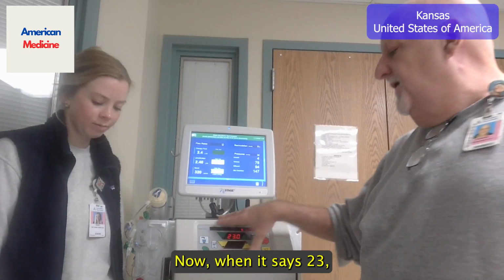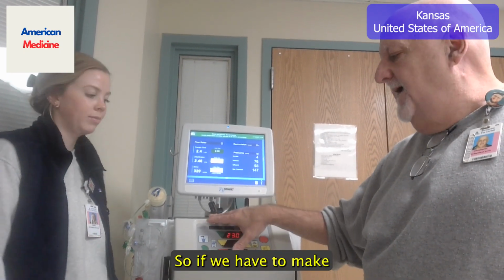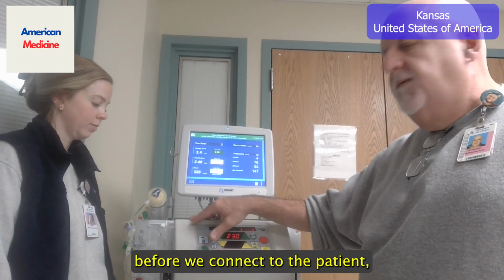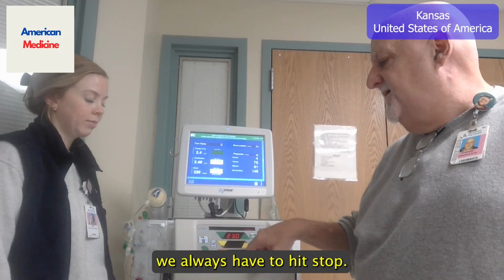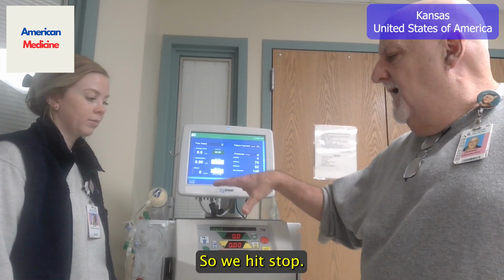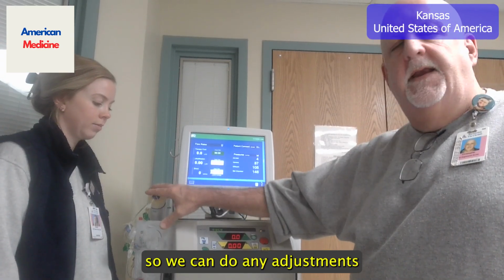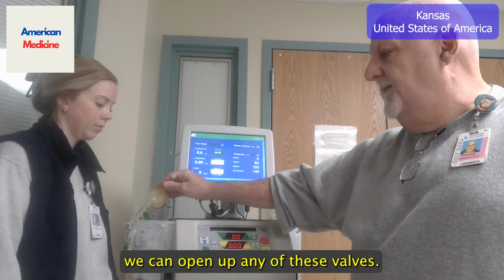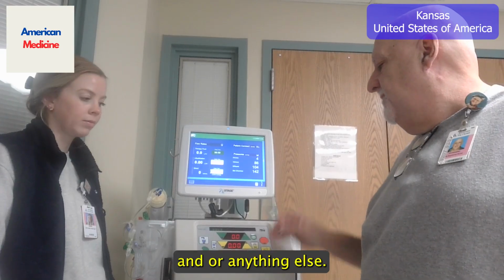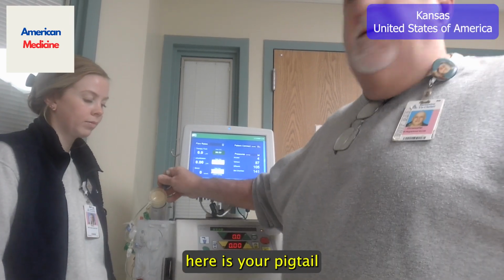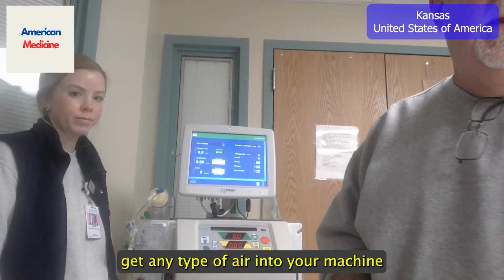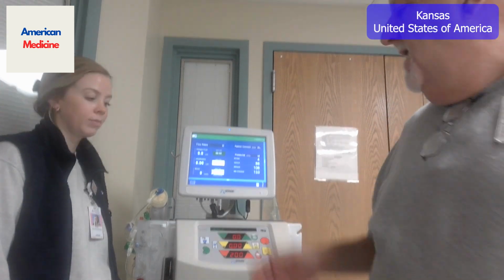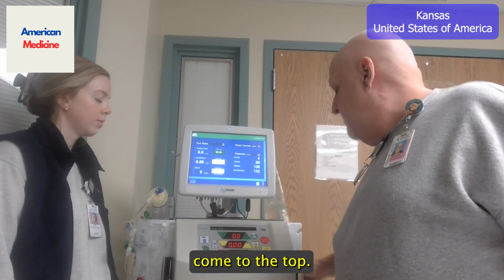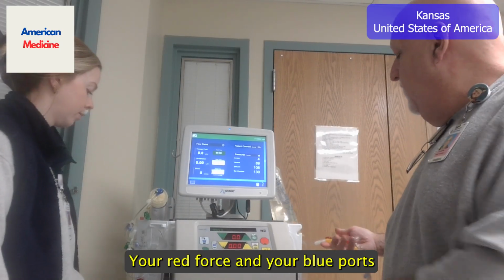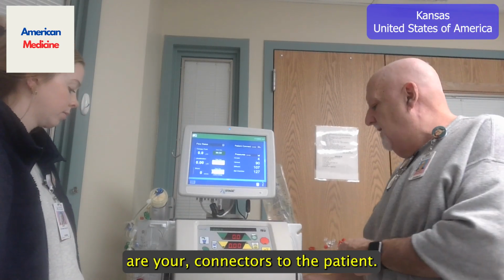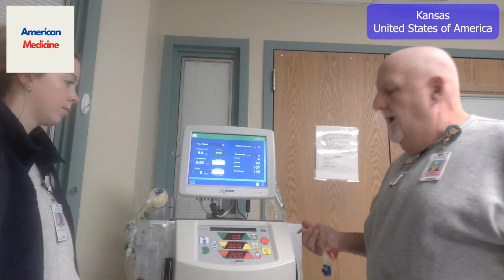Now, when it says 23, the pump's still running, so if we have to make any adjustments on this before we connect to the patient, we always have to hit stop. So we hit stop. The pump has stopped running, so we can do any adjustments we need to make at this point. We can open up any of these valves. It won't suck air in or anything else. So like I said, here's your pigtail where you'll take air out. If you get any type of air into your machine, it will get trapped in the filter and come to the top. Your red ports and your blue ports are your connectors to the patient.